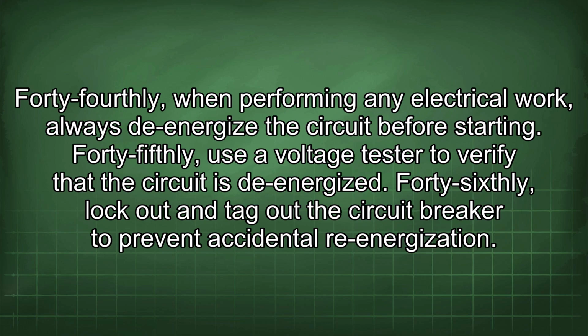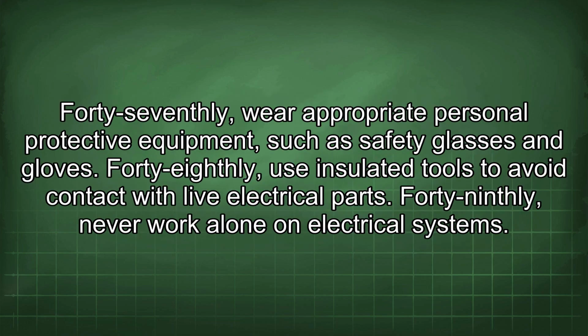44thly, when performing any electrical work, always de-energize the circuit before starting. 45thly, use a voltage tester to verify that the circuit is de-energized. 46thly, lock out and tag out the circuit breaker to prevent accidental re-energization. 47thly, wear appropriate personal protective equipment, such as safety glasses and gloves. 48thly, use insulated tools to avoid contact with live electrical parts.